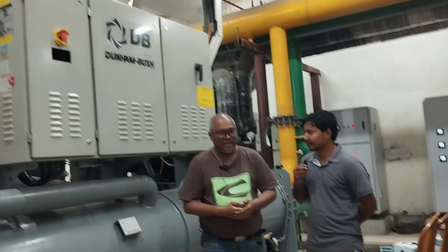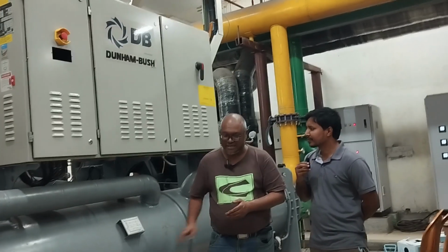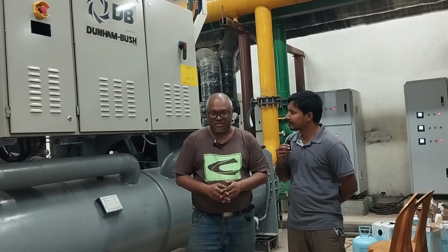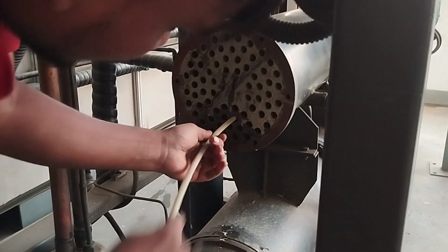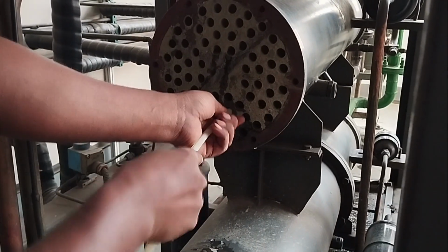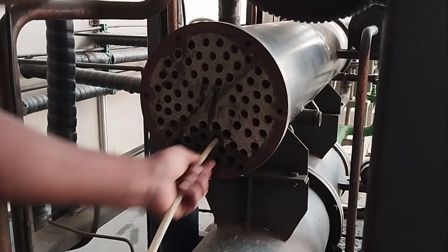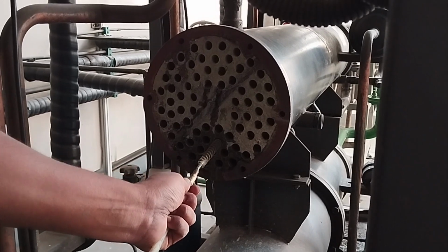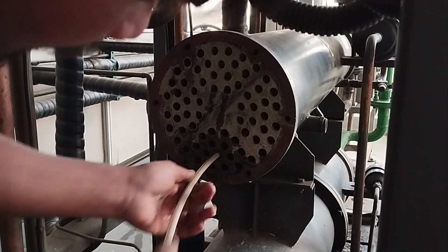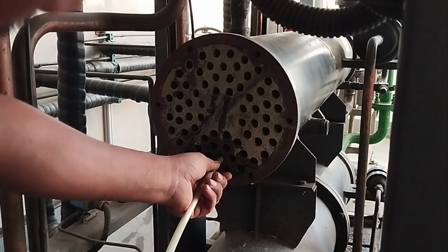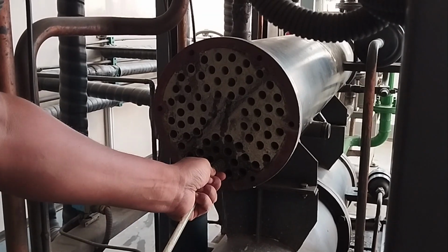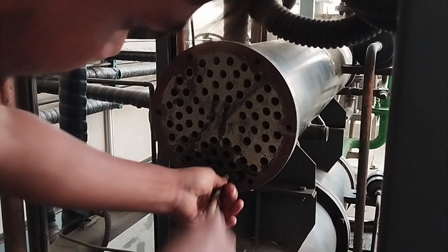Secondly, the condenser tube and the cooler tube. What we propose is, if the condenser approach is higher than 5 degrees Fahrenheit above the normal value, you need to clean the condenser or the cooler tube.